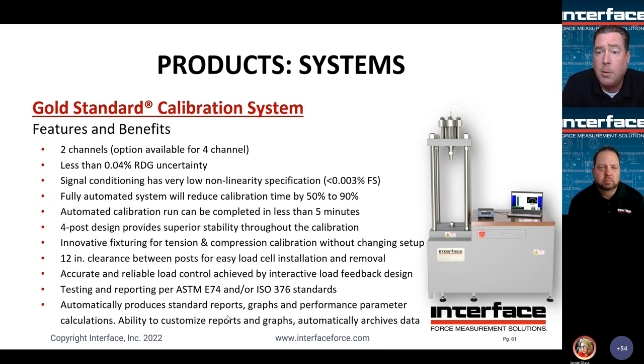Typically speaking, you're going to see, let me back up one step, I'm sorry. This also allows you to run tension and compression in one setup, so there is no removal of the DUT and installation in a different manner or configuration to switch between compression and tension calibrations. It's a single setup for tension and compression, and typically speaking, you're going to see a full 5 or 10 point calibration accomplished in between 2 to 3 minutes. Very quick. Typically, you're going to spend more time installing the DUT into the system than the calibration run itself will actually take. So, yeah, a couple comments on that.